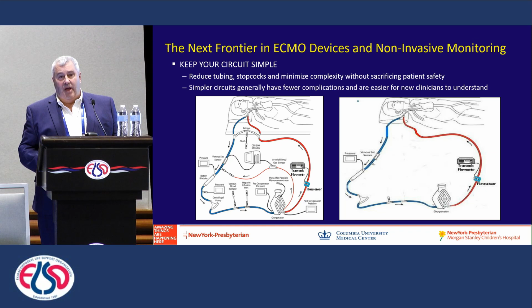And the things that I think about at first when I think about non-invasive monitoring include things like multiple flow probes with bubble detection. Certainly multiple pressures. We measure pressure non-invasively on all the limbs of the circuit. So that's on the drainage limb before it hits the centrifugal pump, between the centrifugal pump and the oxygenator, and then distal to the oxygenator on the reinfusion limb. And there's a whole host of ways that we troubleshoot, and I'm only going to share one or two examples as we move forward. Things like hemoglobin, hematocrit, arterial and venous saturation monitoring, temperature monitoring, near-infrared spectroscopy, certainly continuous monitoring of PO2 and PCO2 in the ECMO circuit.